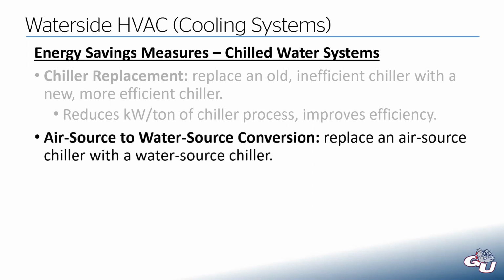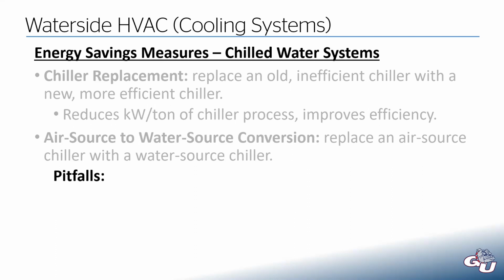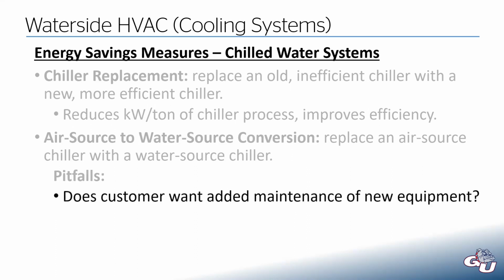Or you could take an air source system and convert it to a water source system. So let's tear out an old air source chiller, put in a water source chiller, because I just explained that a water source chilled water system is going to be more efficient. The things you need to watch out for, though: does the customer want that maintenance? You're putting a lot on the customer's plate to maintain all of that equipment. And do they want to take that on? Do they have a properly trained maintenance staff to take care of that?